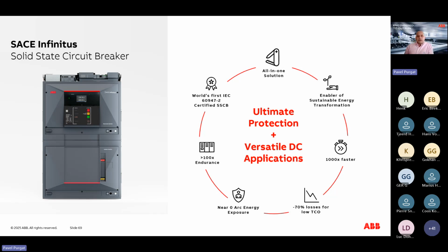Compared to the traditional technology, it's approximately 1,000 times faster, needing on average 20 microseconds to interrupt the short circuit current. Now consider that normal circuit breakers need 20 to 40 milliseconds, depending, of course, on the current rating. Compared to other semiconductor current limiters, it is extremely efficient because it's using proprietary reverse blocking IGCTs that were developed especially for this application. Because of the super fast speed, there is almost no arc energy, so the arc exposure is eliminated. And since we have moved the electrical operations to the semiconductor, the endurance was dramatically increased. Traditional technology needs replacement after a certain number of electrical operations. With the switching of the semiconductor part of the Sace Infinitus, this is no longer needed.